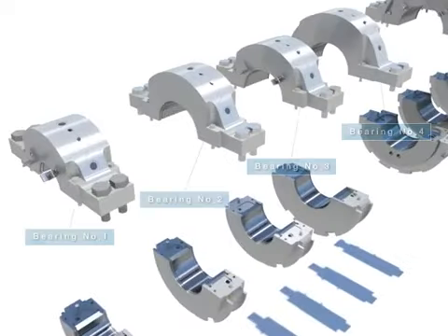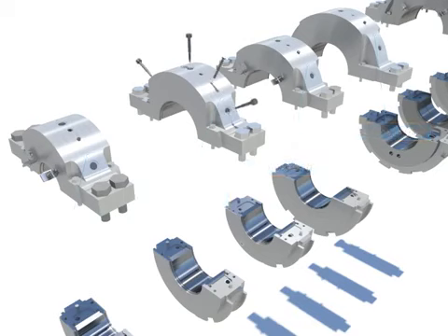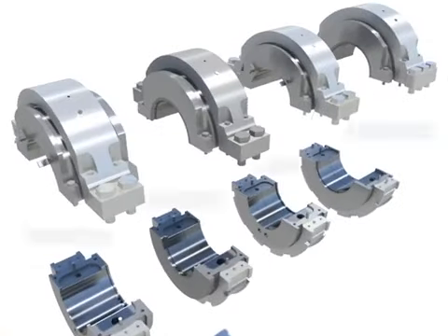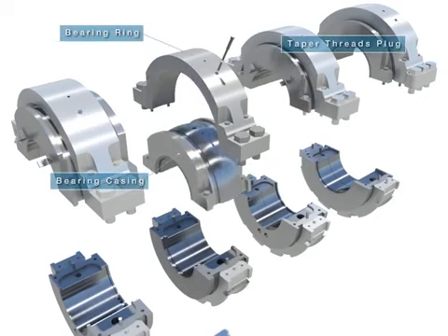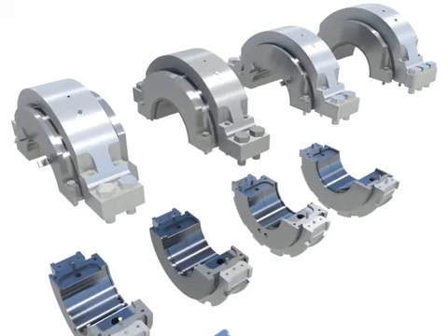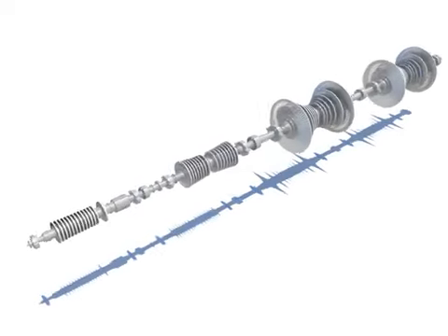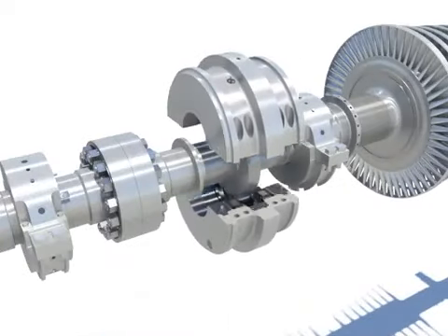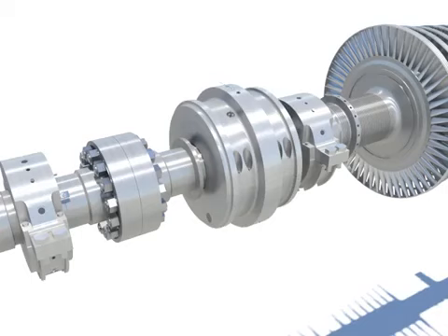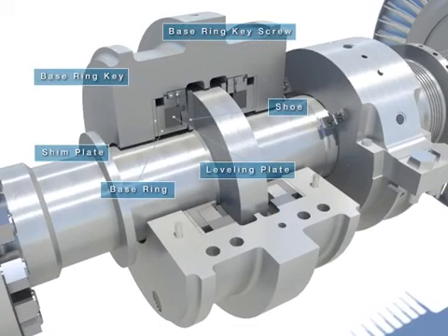The bearing is an equipment which sustains the weight and thrust of the turbine rotor. Number 1 to number 4 bearings consist of the double tilting pad type. Number 5 to number 8 bearings consist of the elliptical type. The thrust bearing is located between number 2 and number 3 of the journal bearing and prevents the movement of the turbine axial, which has exceeded the limit.